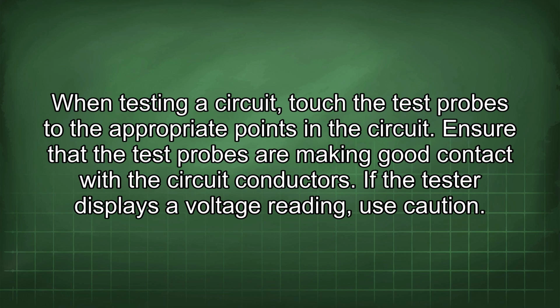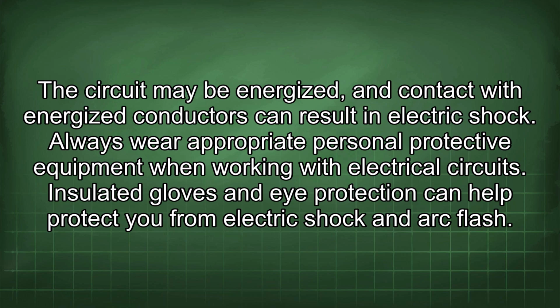If the tester displays a voltage reading, use caution. The circuit may be energized, and contact with energized conductors can result in electric shock. Always wear appropriate personal protective equipment when working with electrical circuits. Insulated gloves and eye protection can help protect you from electric shock and arc flash.